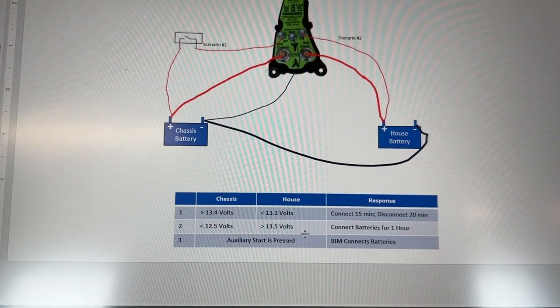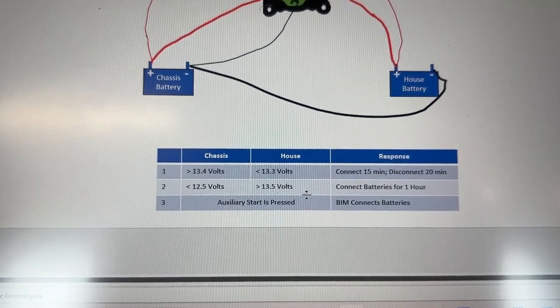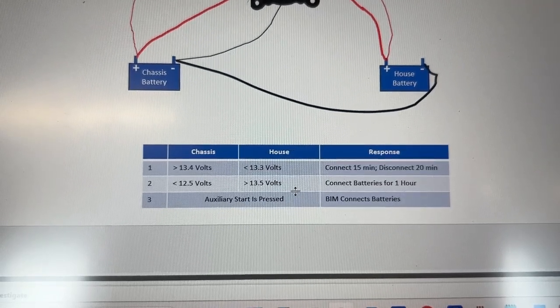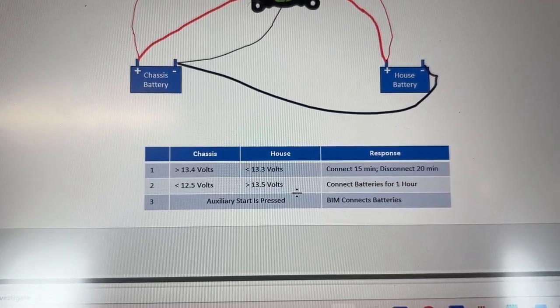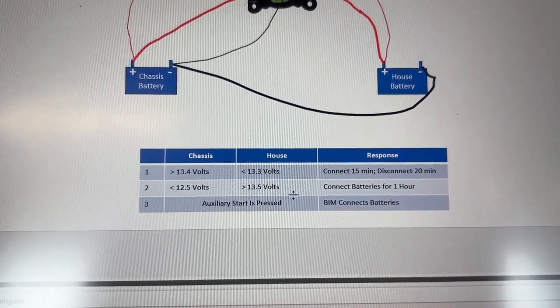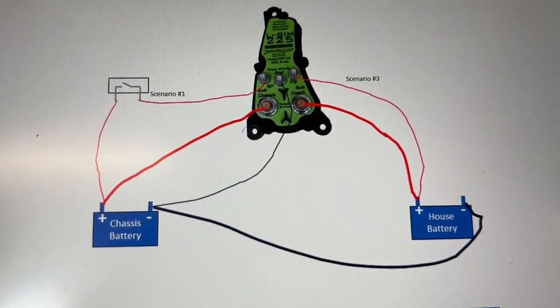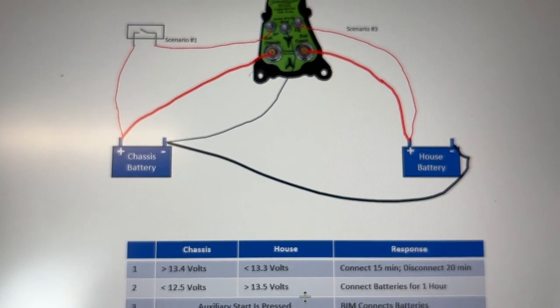We've done scenario one and scenario two. Scenario one: chassis battery large, house battery small — driving along the road — verified it connects for 15 minutes and disconnects for 20. Scenario two: chassis battery weak, house battery strong doing a trickle charge into the chassis battery as when sitting — connected for one hour then disconnected for two minutes. The last scenario is the auxiliary start: when a positive wire from the house battery is connected to the signal of the BIM, it closes the circuit so the house and chassis batteries are connected.